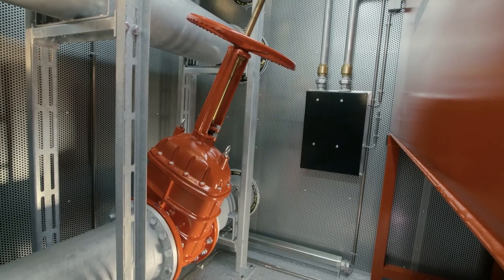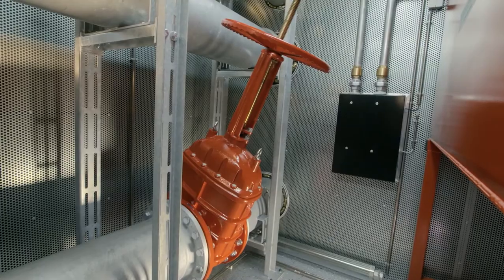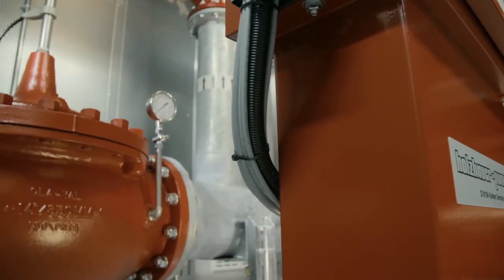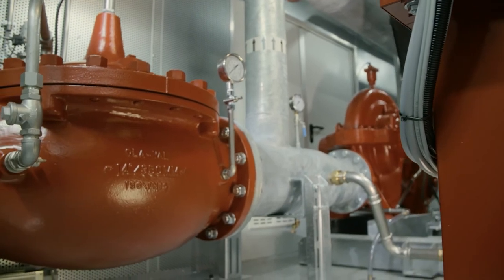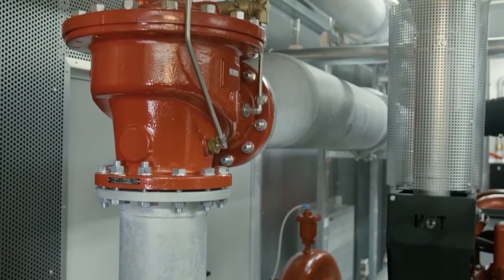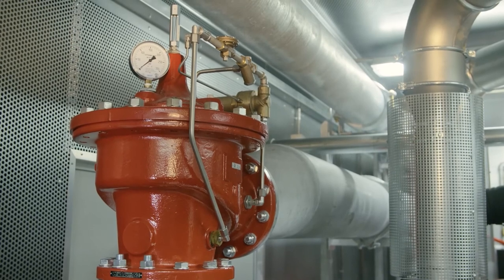With respect to operating and safety valves of the pump group, Holzhauer Pumpen fulfills the most stringent requirements of the applicable regulations. On the discharge side, a pump start-up valve with a backflow preventer function reduces start-up pressure bursts in the discharge piping. The discharge piping is also protected by a main relief valve according to NFPA requirements, equipped with a position indicator.